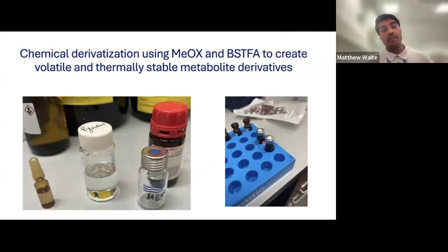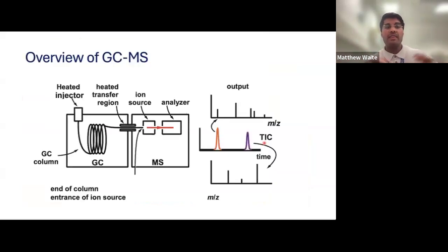Now, you've prepared your samples. That takes about 6 hours. And then once you've prepared your samples, you then begin loading them on the GCMS. That is probably one difference between GCMS and LCMS. From my understanding, learning, and experience, the preparation of samples with GCMS is generally longer than that of LCMS. So I find this diagram quite helpful for seeing an overview of gas chromatography mass spectrometry.